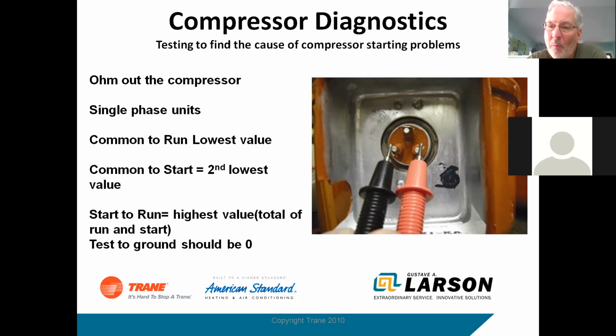So if you ohm out the common to run low value, the common to start second lowest value, and add those two numbers together, start to run should equal that number. Okay, and of course, ground should be 0.